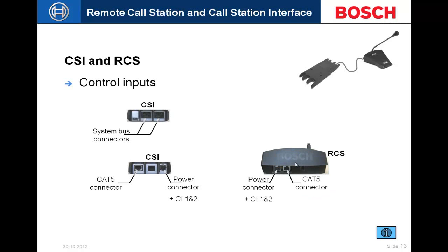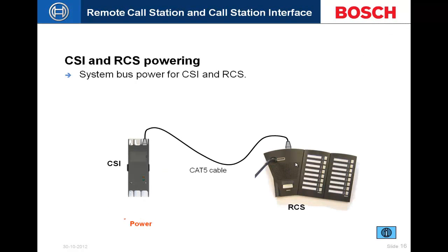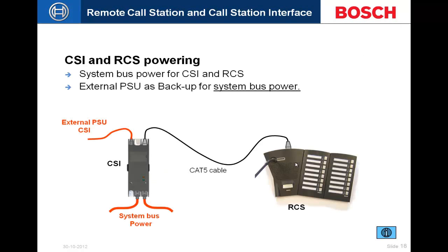On the rear of the RCS, there is a CAT5 connector, a power connector, and a small RJ12 connector used only as a factory programming port. On the CSI, two system bus connectors give the ability to insert it within a supervised ring topology fiber system. An external power supply can be connected to the CSI, and an internal jumper selects external power for the remote call station.